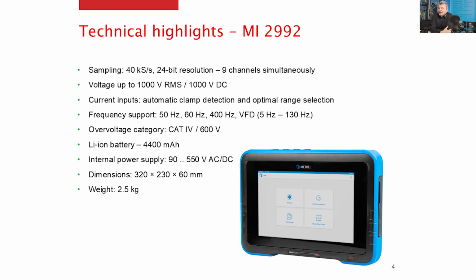If we are focused on technical highlights, we need to mention that we have a sampling frequency of 40 kilohertz, 40 kilosamples per second, compared to the previous portfolio, which was only 7 kilohertz. And we use inside 24-bit resolution. And we need to point out that we are analyzing all 9 channels simultaneously. Why 9 channels? We have 4 current inputs and 5 voltage inputs.